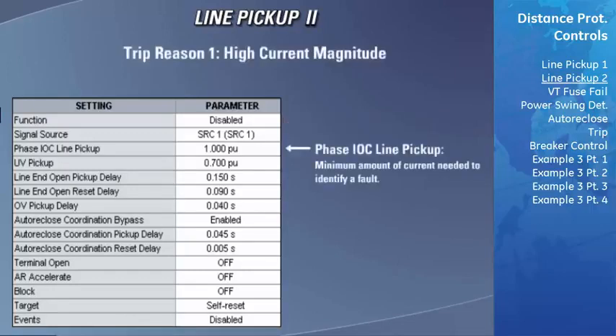This setting should be set to the same source that the distance elements are using. If the transmission line you are protecting has a strong source, the phase IOC line pickup field needs to be set to the minimum amount of current that needs to be present to adhere with the first method of detecting a fault, that is, having a very high magnitude of current. This setting needs to be set higher than the maximum amount of current that will be seen during normal inrush conditions. If the transmission line you are protecting has a weak source, this phase IOC line pickup setting needs to be set low enough to detect the levels of fault current that will occur on weak systems. You will note that this setting will be lower than the normal inrush current.